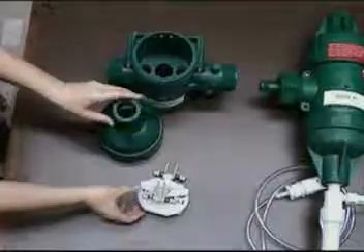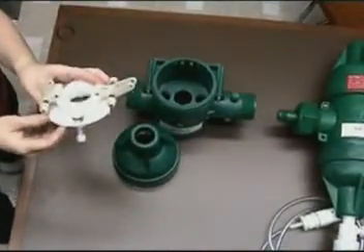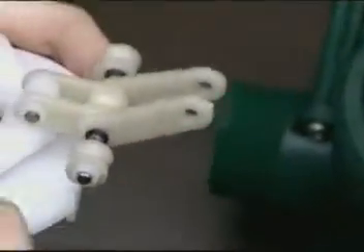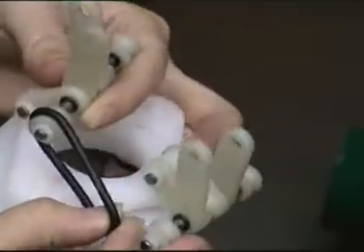The valve module is activated by the tension bands to redirect the water flow at the top and bottom of each stroke of the piston. This redirection is the snapping sound that is heard when water is flowing. These tension spring bands are 50% heavier than on other medicators, and they run on roller bearings to reduce wear.